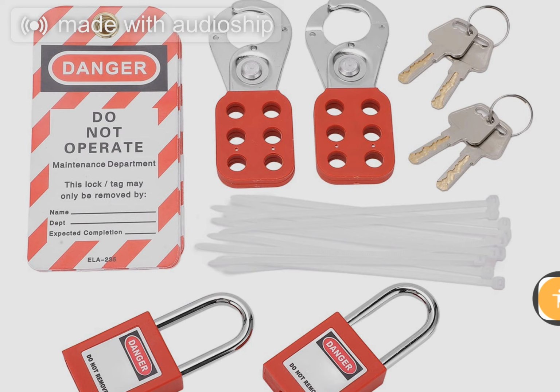We're talking about standards like NFPA 70E. And it's not just a guideline, it's really the benchmark. It tells you the absolute minimum safe clearance you need based on the voltage. So the boundaries are step one, but the real game changer, the thing you do that removes all doubt before you touch anything, is making sure the power is actually off. This is where we go from theory to life-saving practice. It's the single most practical step, and the source material calls it the three-point test.